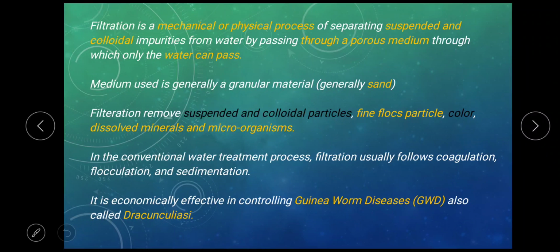Now coming back to filtration. Filtration is a mechanical or physical process of separating suspended, colloidal and dissolved impurities from water by passing it through a porous media. We generally use a porous media, a sand grain, through which only water can pass. Now, the media used is generally a granular material, that is sand. This filter removes suspended solid, colloidal particles, fine flocs, color, dissolved organic impurities, and microorganisms.